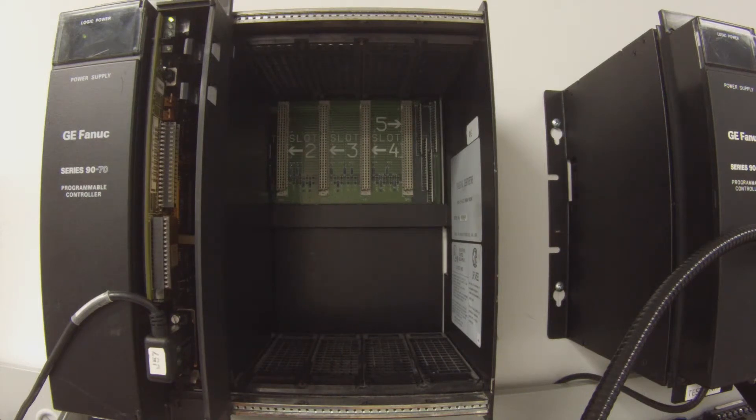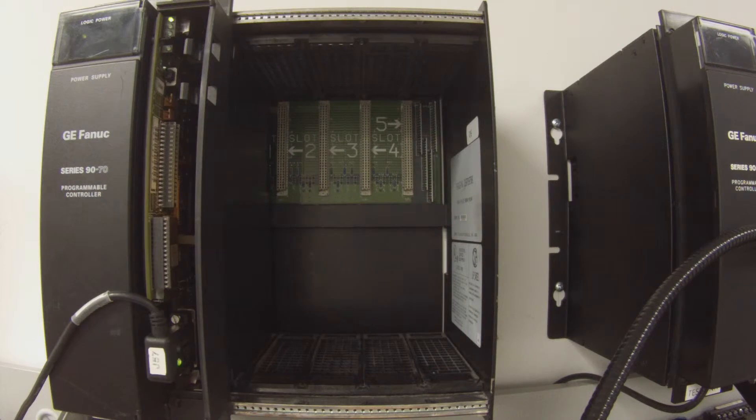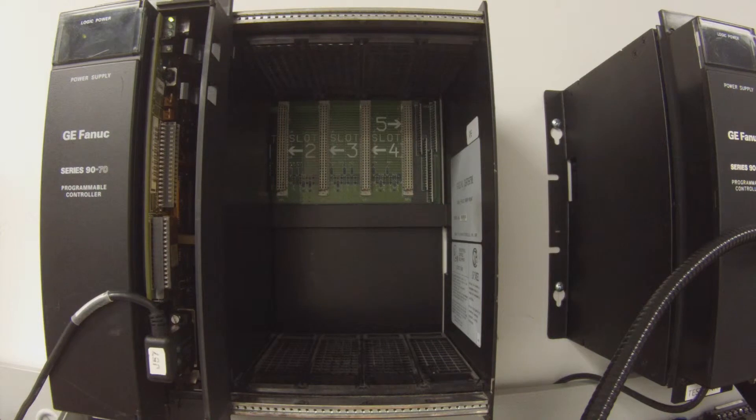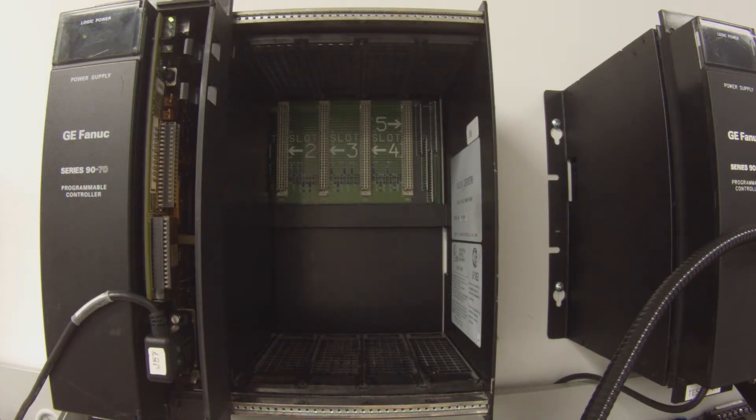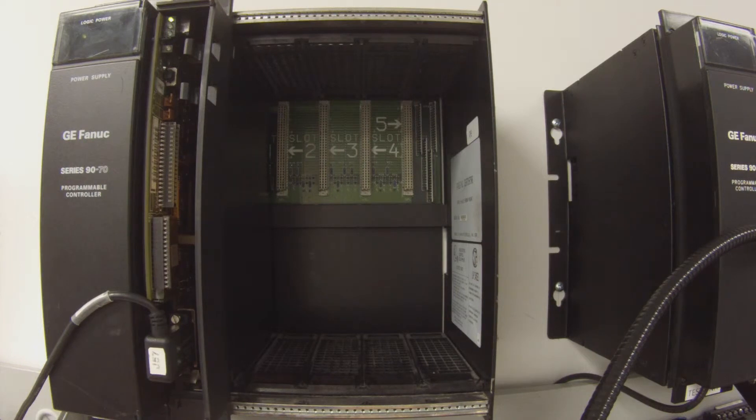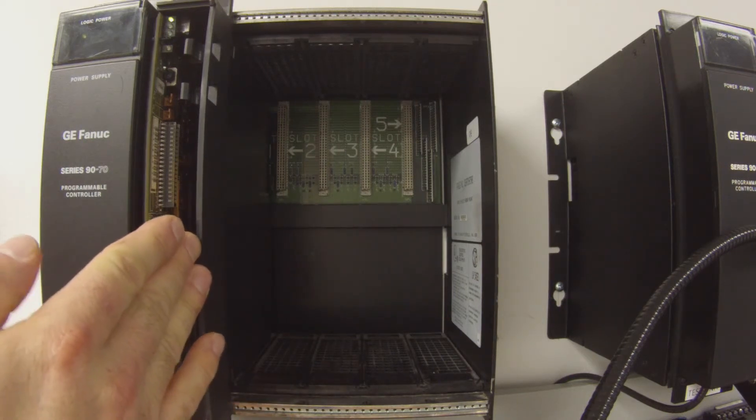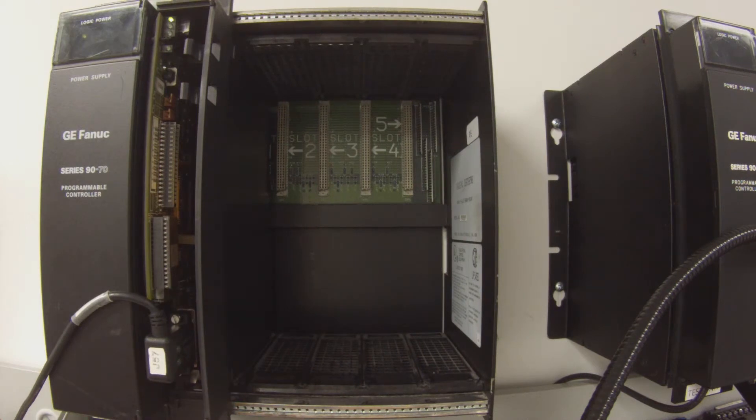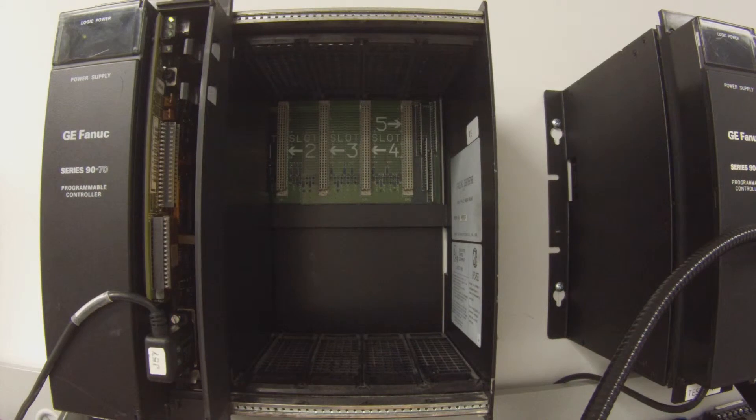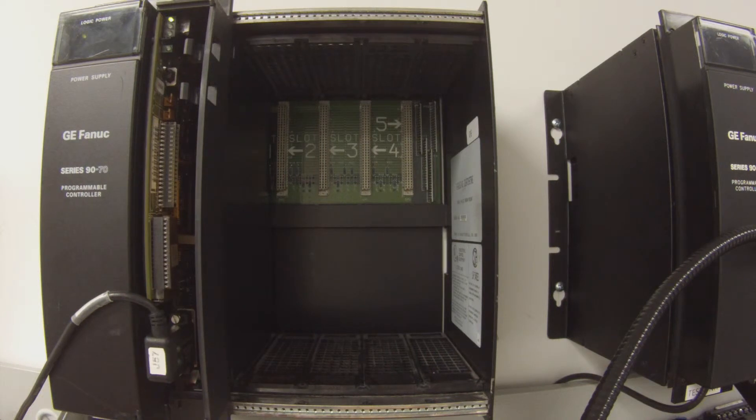The next thing is once that is clear, go to the download and run icon, download information and run button. The first thing that comes up is asking us what is it that we want to download. So again, just a simple test, our goal is to get the processor into run mode and all we want to download is controller, hardware configuration and logic. So the top two selections, hardware configuration and logic, and then yes.